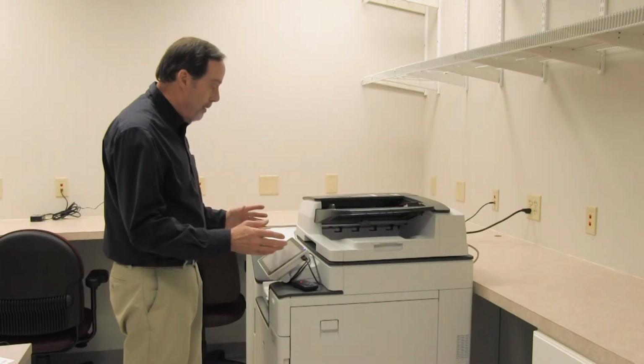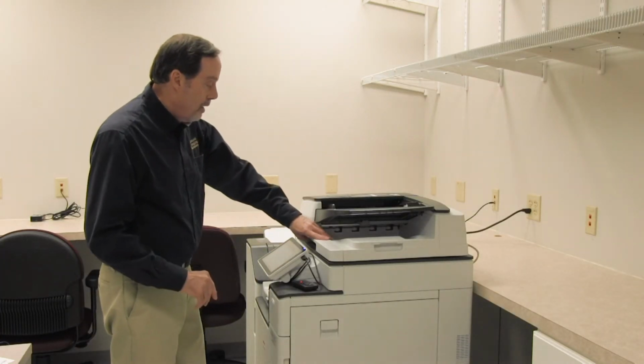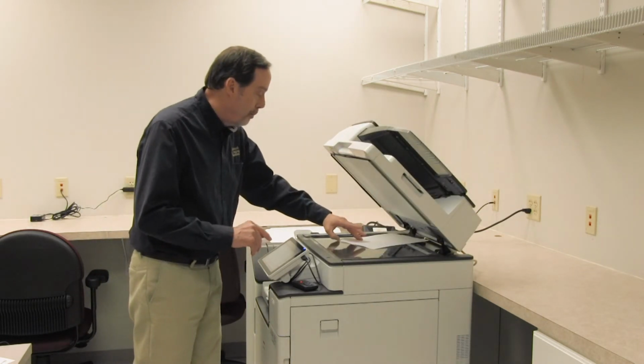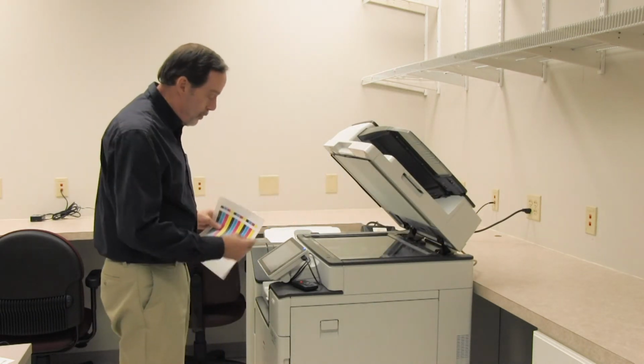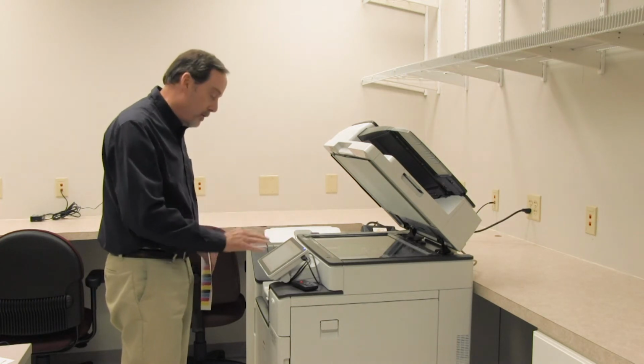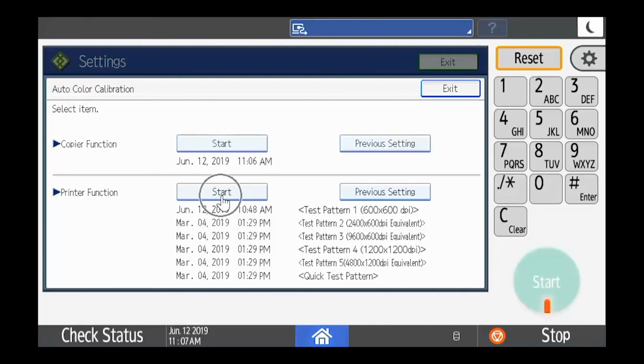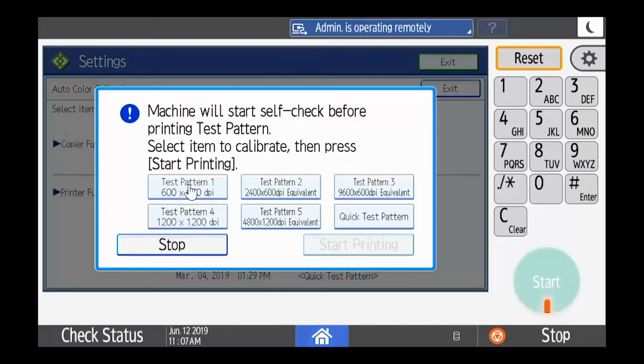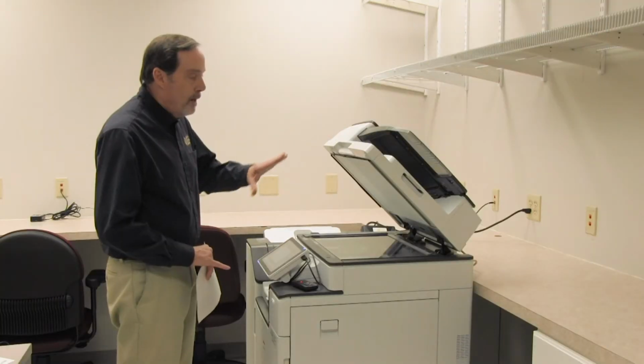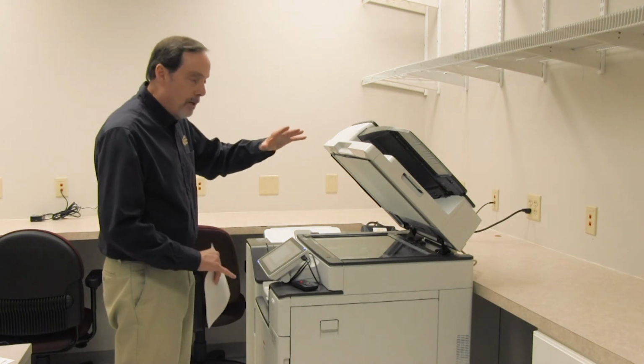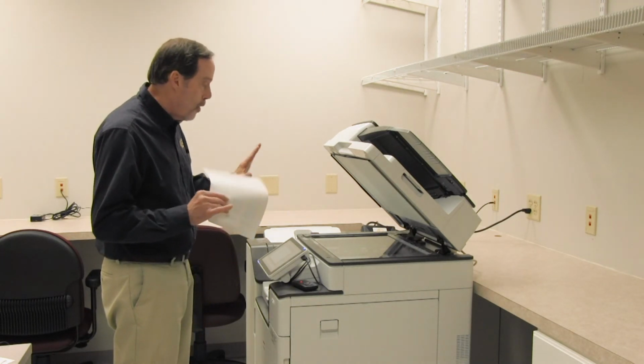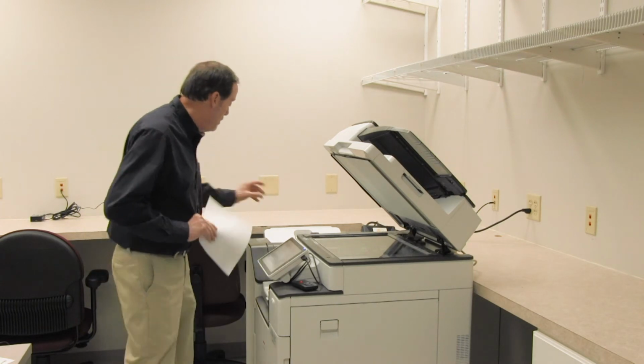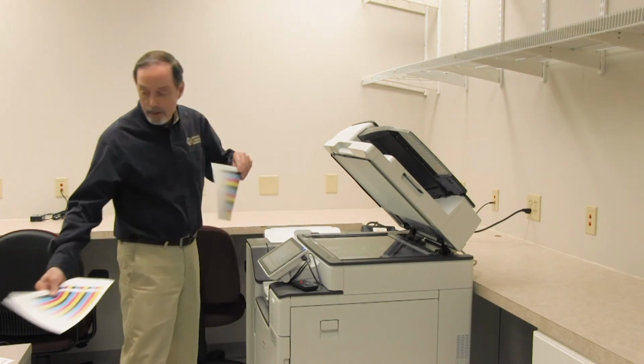While it's doing that, during the scanning process, and also during the printing process, that takes care of the copier function. Now we're going to do the printer function. And there's going to be 5 sheets we're going to print out. So we're going to hit start, and you're going to select test pattern number 1. Then you hit start printing. While it's printing, you don't want to adjust, you don't want to lower the doc feeder, you just want it to be in a stationary state without anything happening.